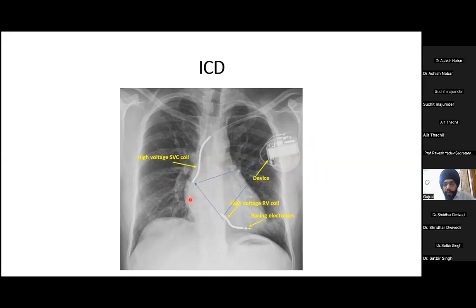So this device can shock through three vectors. Whenever energy is to be administered, there have to be two poles. The first vector, the most commonly used, is from the RV coil to the CAN, or the pulse generator. The second vector, available if you have a dual coil ICD, is from the SVC coil to the CAN. And the third vector, rarely used, is from the high voltage RV coil to the SVC coil.